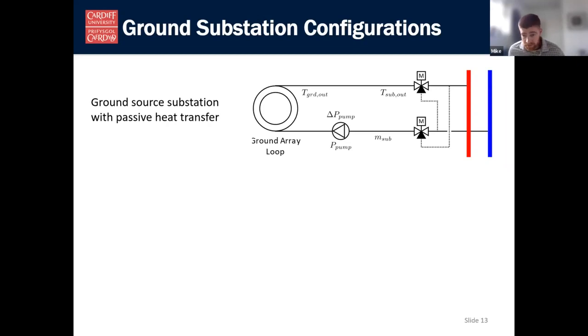So within the simulation, we have a number of base components such as heat pumps, chillers, heat exchangers, etc. And we can take these base components and configure them in various ways depending on how the nominal pipe temperature is controlled in the network. So, for example, if we had no control of nominal pipe temperature, meaning that it just varies with the temperature of the ground source, then the substation for the ground source would consist of just a simple pump and 3 port valves, which are used to direct water around the array and into either the warm or the cool pipe.